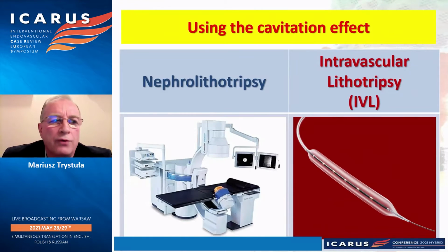The effect of lithotripsy is based on the cavitation phenomenon, in which the static pressure of the liquid reduces to below the liquid's vapor pressure, leading to the formation of small vapor-filled cavities in the liquid. When subjected to higher pressure, these cavities, called bubbles, collapse and can generate shock waves that may damage the structure of the calcified solid tissue.